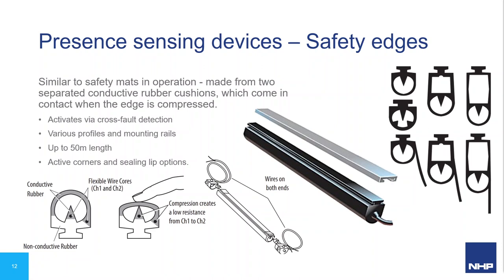Safety edges are also pressure-sensitive safeguarding products designed to detect the presence of people or objects. When compressed, two conductive rubber layers create a low-resistance short that trips the safety control system. They're used on the edges of machinery so a person contacts the safety edge before reaching further into a hazard. A great application is roller doors — if the door comes down and its safety edge contacts someone, the system halts or reverses the motor. Safety edges come in various shapes and sizes based on cushioning factor and angle of actuation, and versions with sealing lips are available, perfect for preventing rain and dust beneath roller doors.